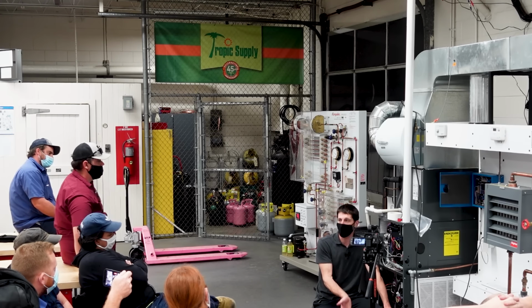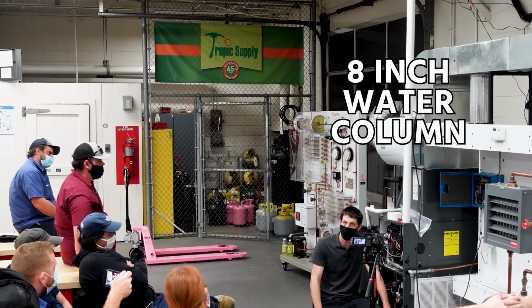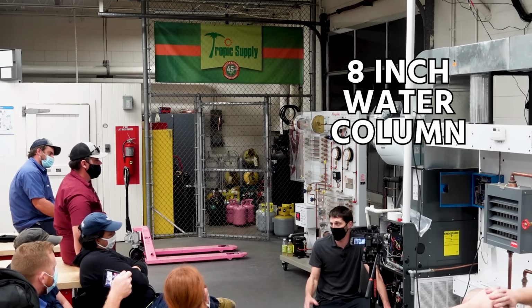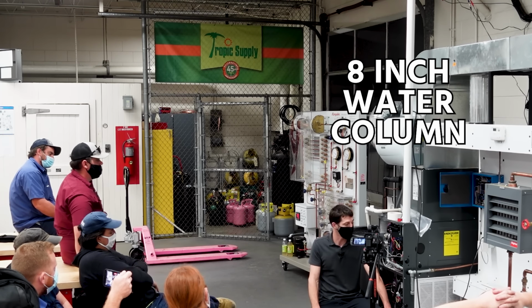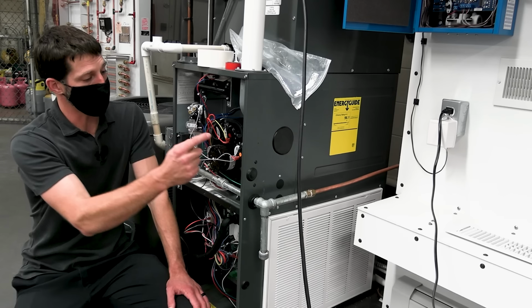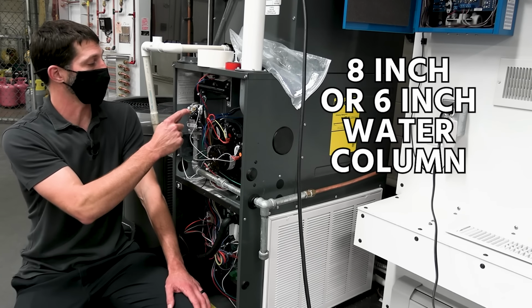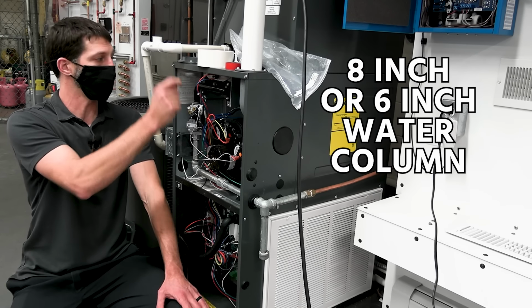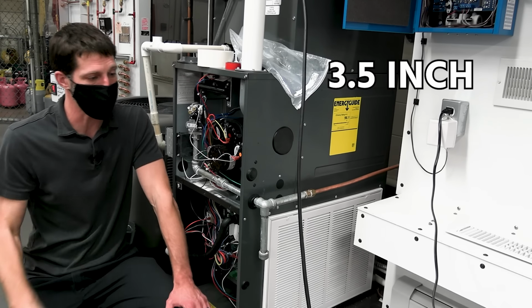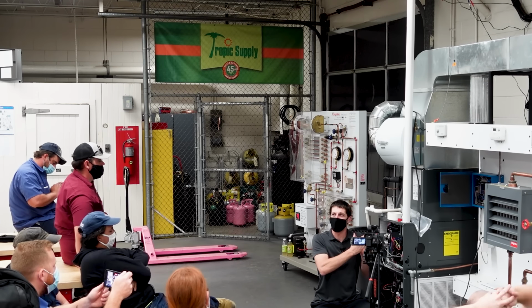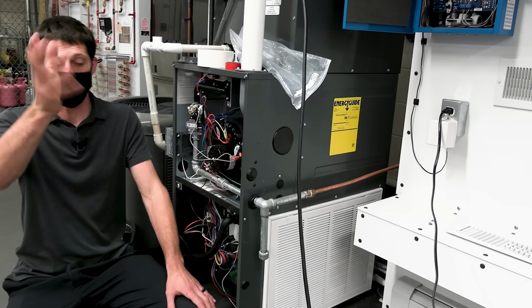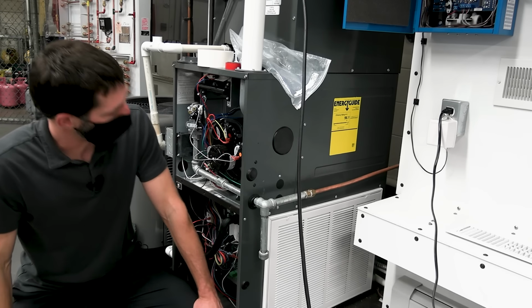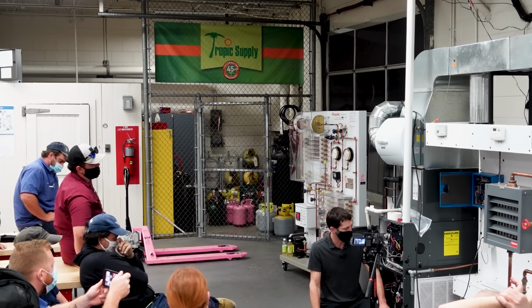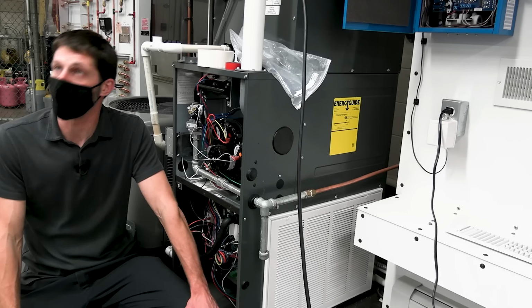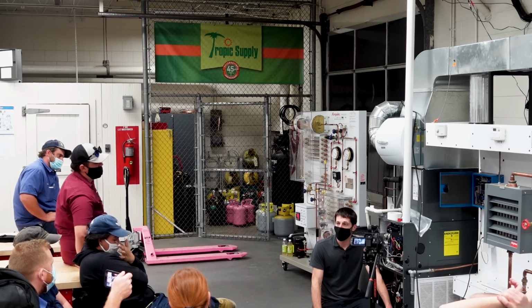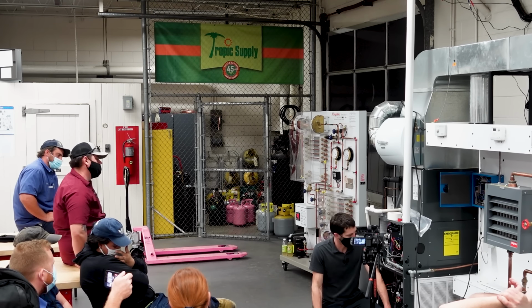Commercial sites, you might see them increasing it to 8 inch water column or something like that, because the gas lines weren't sized properly to begin with, so you run into that as well. But this regulator, even if it's 8 inch water column or 6 inch water column, will still reduce it down to whatever the 3.5 inch. That's not to say that you shouldn't check it again if they were to make a regulator adjustment at the outdoor regulator, but they do have a variety of input water column for gas. And it's inches of water column. So anytime you see WC, that's different than on a recovery tank, where it's water capacity.